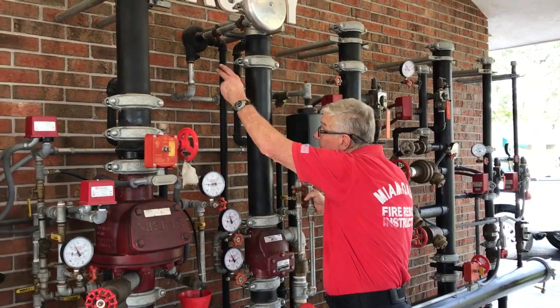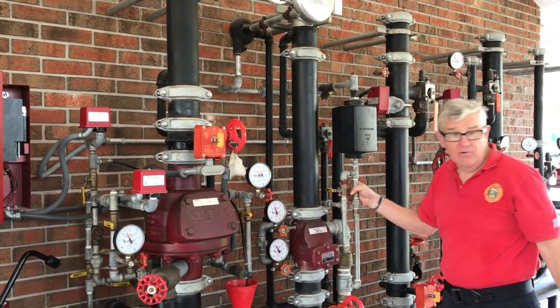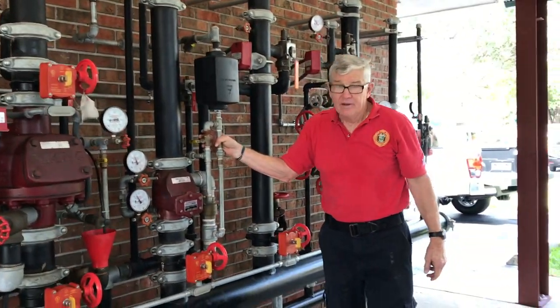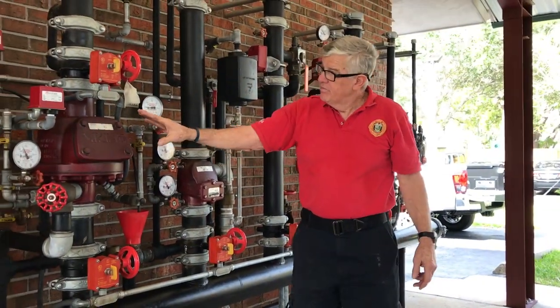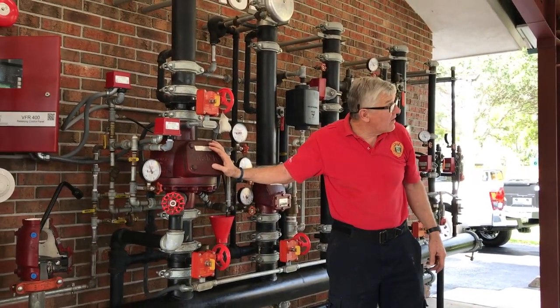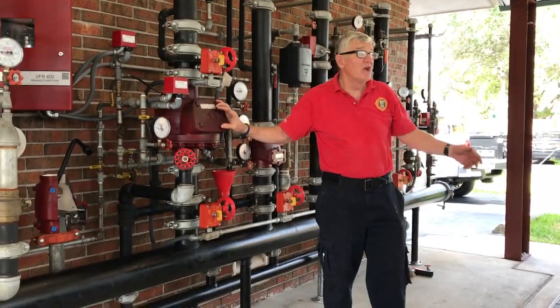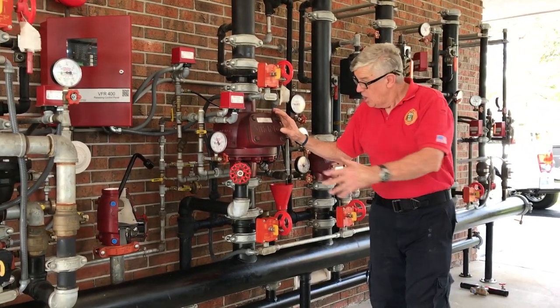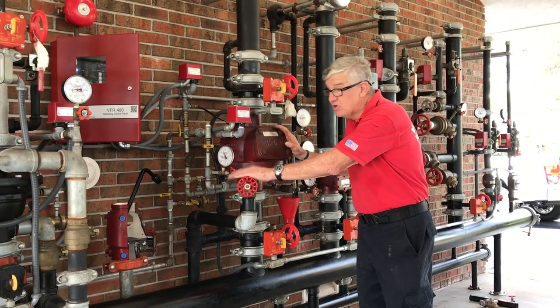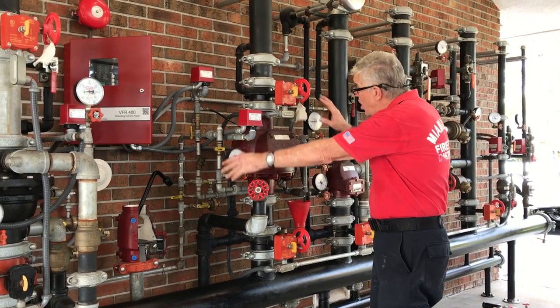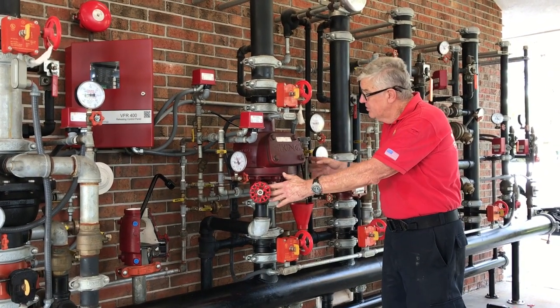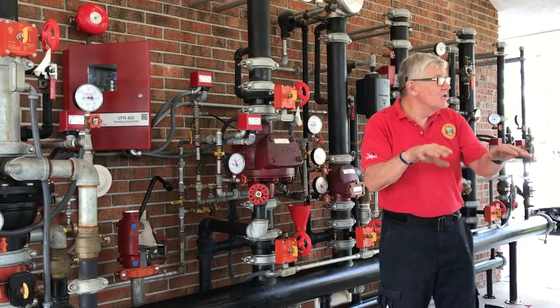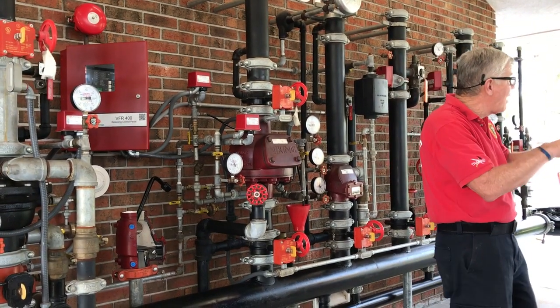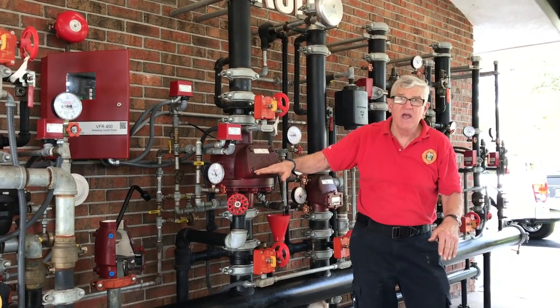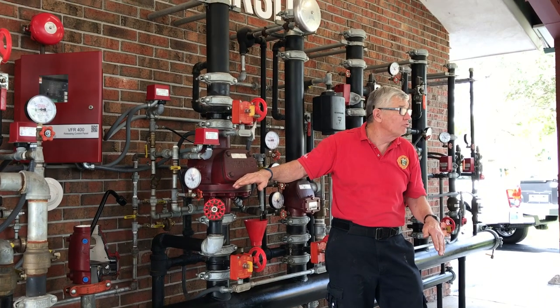Old school, this would drain out on the ground. Now, this is a dry pipe valve. This is used in freezing environments. This would consist of a dry pipe valve, what we call trim. There is air in this system, not water, air in this system that is holding a clapper valve closed.